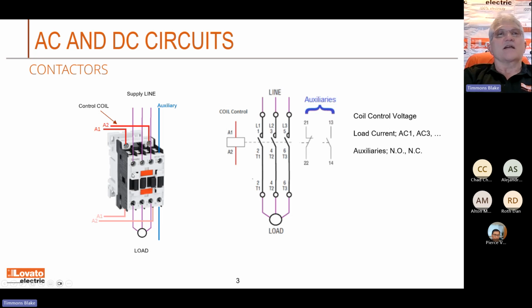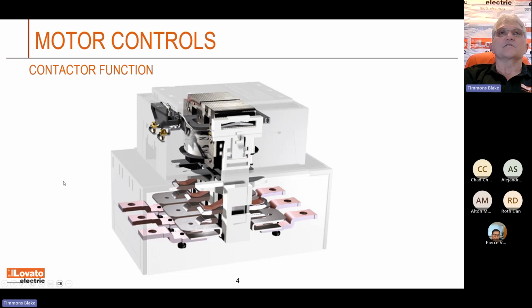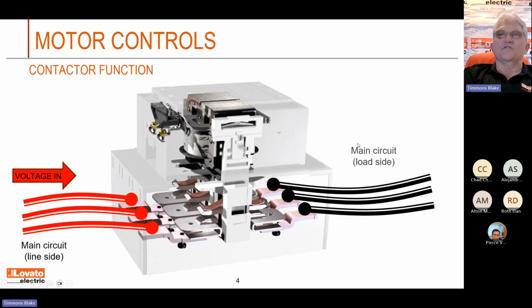Now, when you look at our contactor over here to the left, I've tried to identify some of these terminals. You can see the coil kind of down in there in the back, and that's your A1 and A2 terminal. We also feed the bottom, so we have an A1 and A2 terminal down there also. Then you can see with the blue line the auxiliary contacts that come over to the side. So that said, let's drill in a little deeper on how a contactor works. The first thing you're going to do is land your motor leads and your power leads coming in.